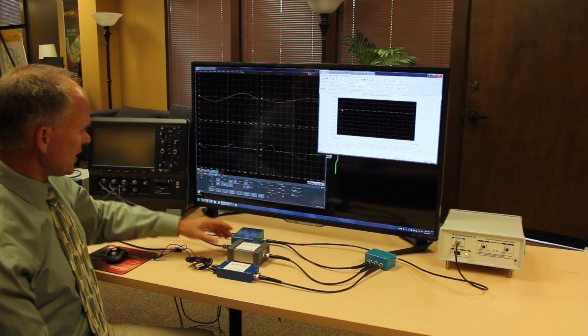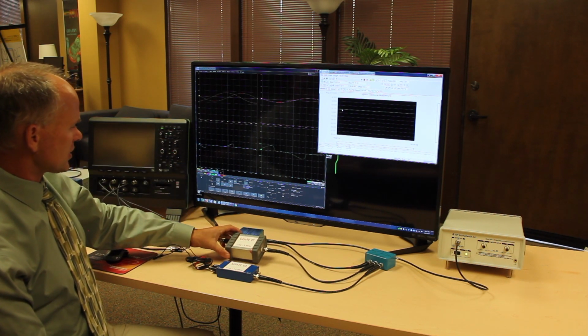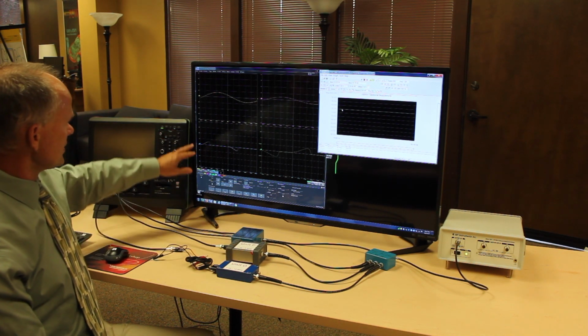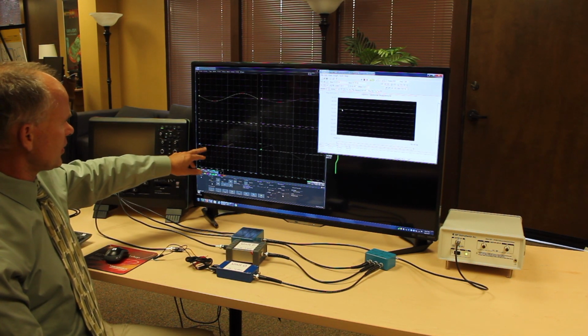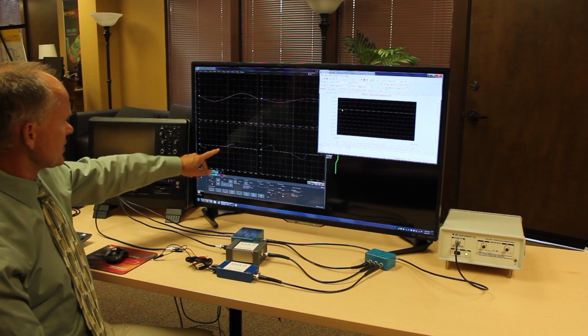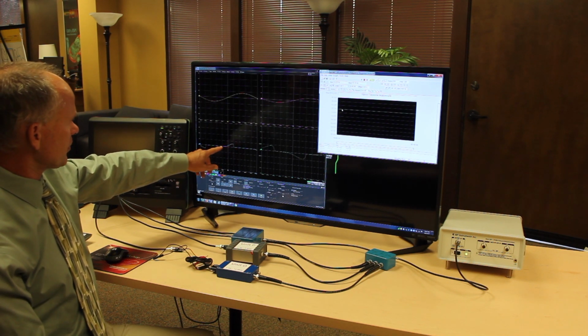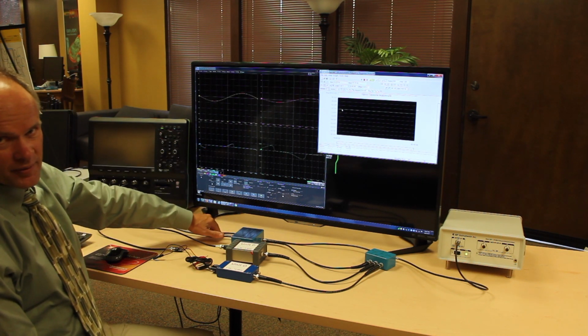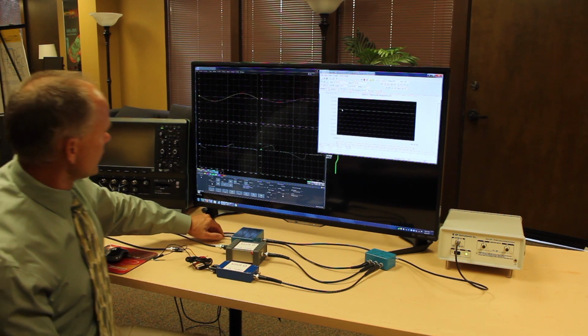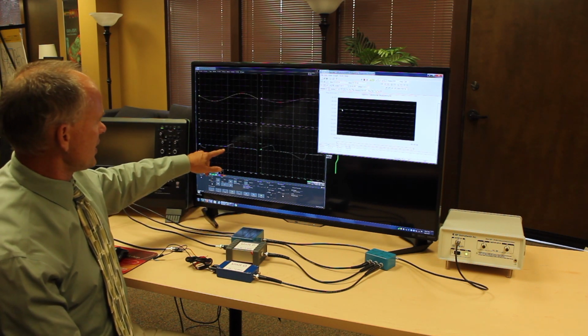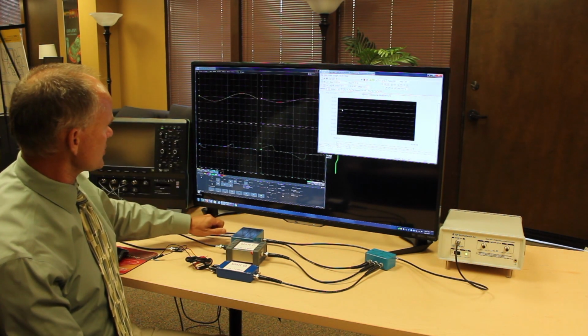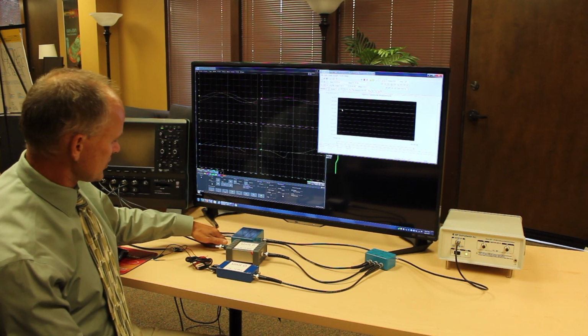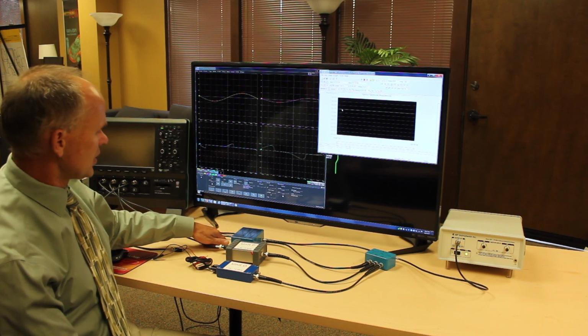On unit P, which is supposed to go all the way down to 1 Hertz, we can see that the transformer is saturating quite badly. Not only is it not giving much signal on the output, but it collapses almost immediately after the sine wave starts. If you try injecting this distorted sine wave into your power supply, you're going to get some very bizarre results.